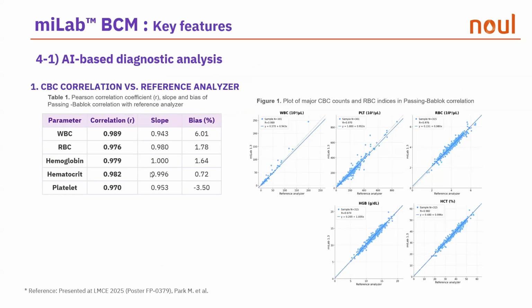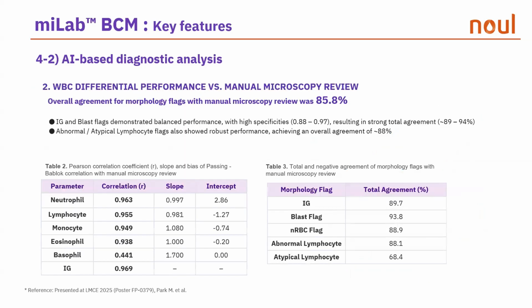So, you can ask, okay, how does the device correlate and agree with the reference devices from a laboratory nowadays? Here I can give you some numbers about correlation regarding the CBC parameters compared with the reference analyzer installed in the laboratory. The NOUL team always uses gold standard devices to make validation and correlation of our parameters. This device is different from the one that Joel used in his laboratory, which we will present later during our webinar. But here you see a correlation bigger than 0.95 for all the basic parameters from the CBC. And in the next slide, you see the full agreement about the differential and also about the flagging.